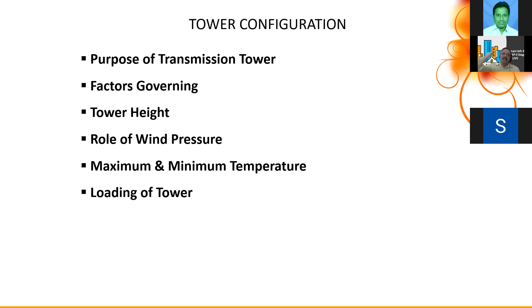Purpose of transmission tower, factors governing the design, tower height. The height of the tower in transmission ranges from 30 meters to 55 or 60 meters. Wind pressure is very critical, along with maximum and minimum temperature and loading on the tower. The project report is prepared with all the recommendations and salient features.